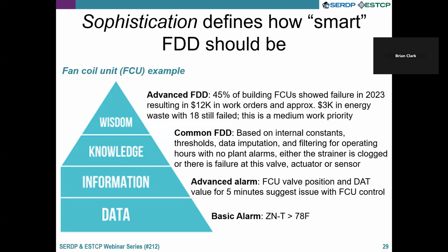As you go up that pyramid, we can get more helpful turning that data into information with things like a basic fault that might be something like, hey, we've been watching your fan coil unit valve position for the past 15 minutes, and based on your discharge air temperature sensor on the other end of that coil, it doesn't really seem like anything's happening that you want it to happen. So we don't know exactly what it is, but we're going to give you a list of possible diagnoses. It could be a clogged strainer, it could be a faulty valve, could be a pinhole leak, or it could be a faulty sensor. As we keep going up, we can get more and more advanced with systems that will deal with data gaps and impute different values to make sure those aggregations have meaning as they get rolled up, or even knowing how to filter when certain conditions don't have operating hours that you would want to count certain faults, and being more detailed with those diagnoses.